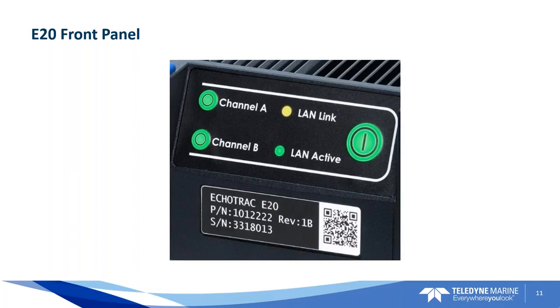Okay, also on the front panel you have these blinking lights. These blinking lights will tell you about the activity of the Echosounder. The flashing yellow light for the LAN link means there's communication between the computer and the E20 itself. That flashing LAN light is helpful to ensure you've got good network connection between the PC, because if it's not blinking, it's not communicating with the PC. For troubleshooting, you know, let's look at some IP addresses. So it's just really simple, a light telling you if it works or not. And then channel A and channel B, they're going to flash when the unit is actually pinging, so you'll know when it's pinging by the lights kind of flashing on and off. It's transmitting a pulse on those channels when it flashes.